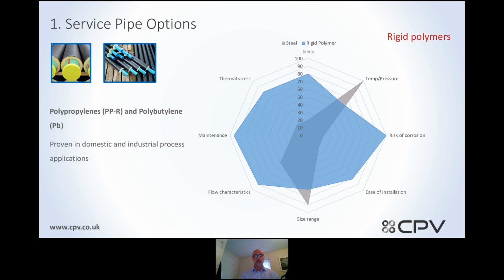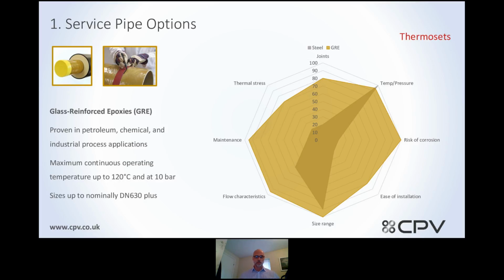Again, you don't need to consider thermal stresses as it's a plastic system. And on the next slide, I'm going to talk about quite a new innovation, which is glass reinforced epoxy. This is typical for higher temperature applications. You'll look at 120 degrees C at 10 bar for 25 to 30 years minimum. It has a larger size range up to 630 mil. That's again the service pipes. A lot of this technology comes from the petrochem industries and chemical industrial processes.